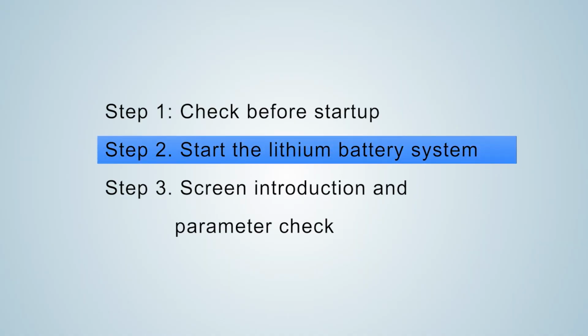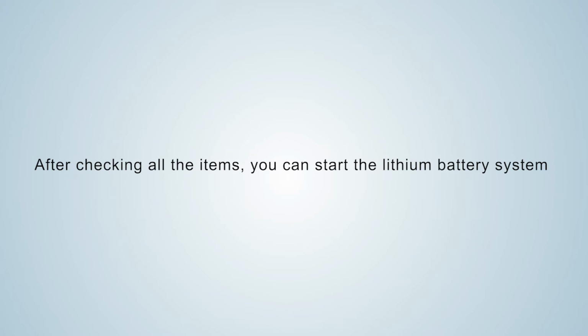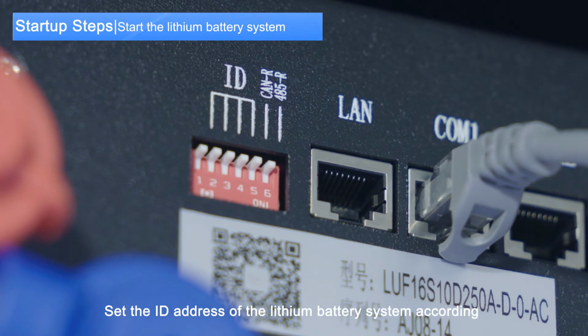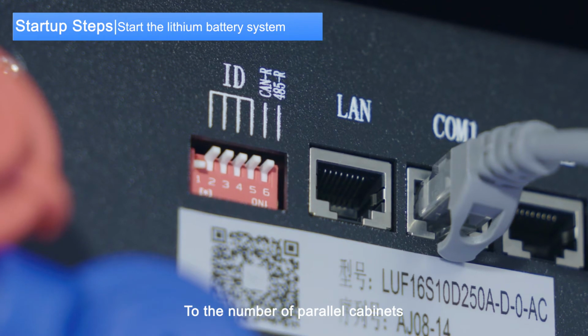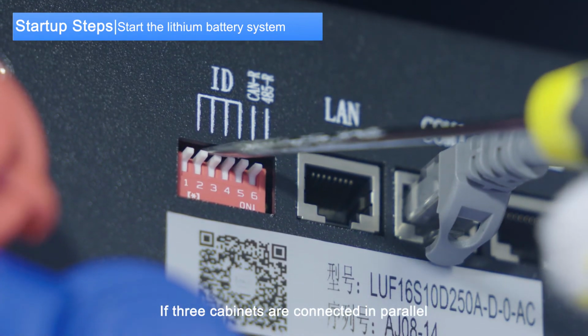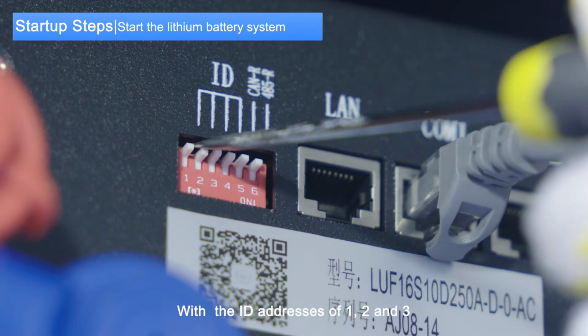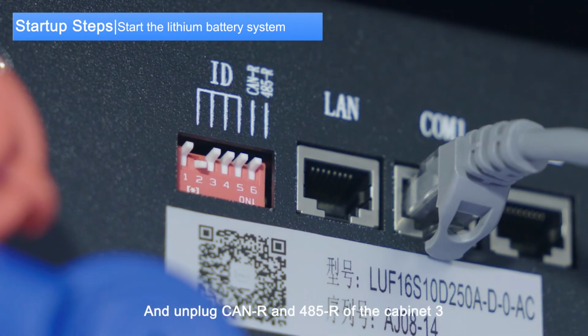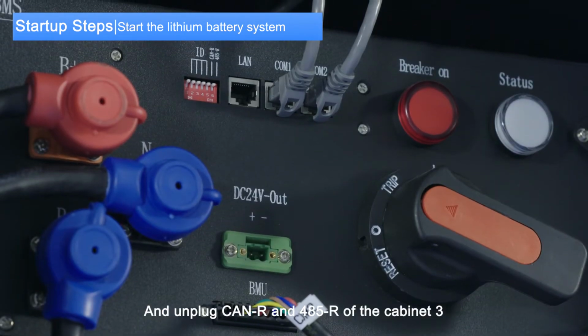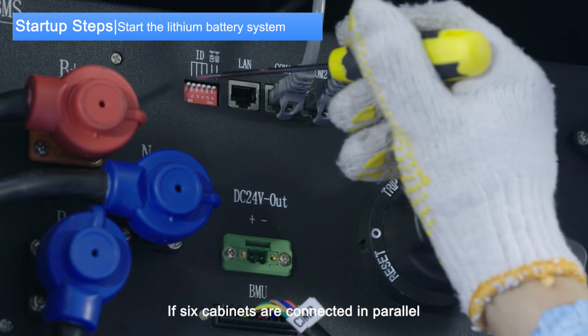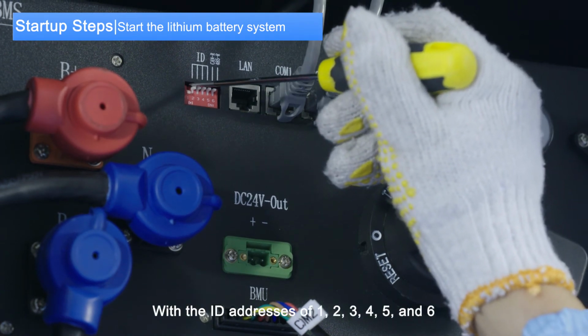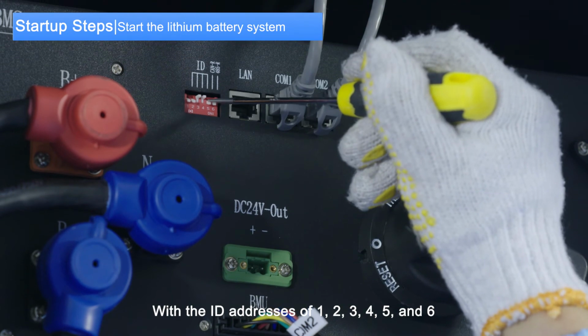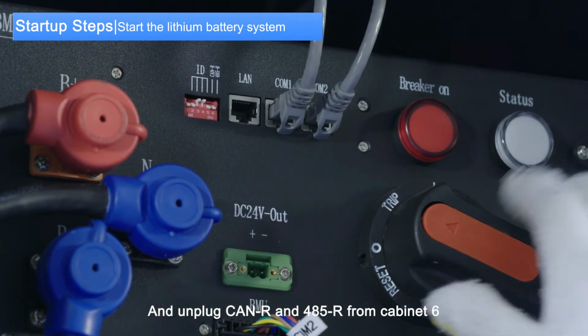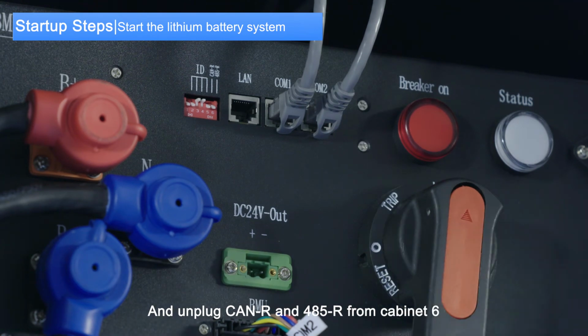Step 2. Start the lithium battery system. After checking all items, you can start the lithium battery system. 1. Set the ID address of the lithium battery system according to the number of parallel cabinets. If 3 cabinets are connected in parallel with the ID addresses of 1, 2, and 3, unplug CAN-R and 485-R of cabinet 3. If 6 cabinets are connected in parallel with the ID addresses of 1, 2, 3, 4, 5, and 6, unplug CAN-R and 485-R from cabinet 6.